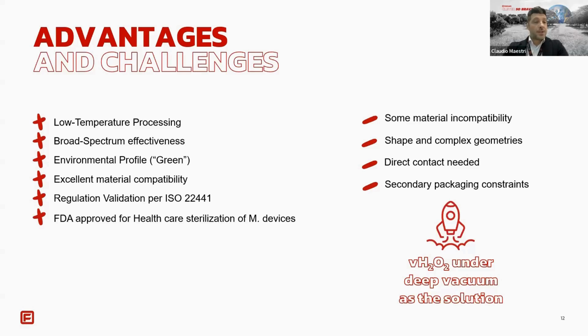Despite its advantages, H2O2 also presents specific challenges that require careful consideration in process development. The first one is some material incompatibility. The primary challenge of H2O2 is incompatibility with cellulosic materials. Cellulose degrades hydrogen peroxide gas, compromising sterilization effectiveness. Additionally, certain uncoated reactive metals like copper and brass may react with H2O2, leading to surface degradation or discoloration. These issues need careful material selection for devices and, critically, for primary packaging. And then some shapes and complex geometries, direct contact needed, and secondary packaging constraints.